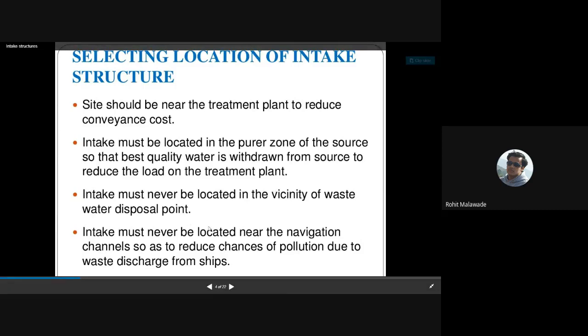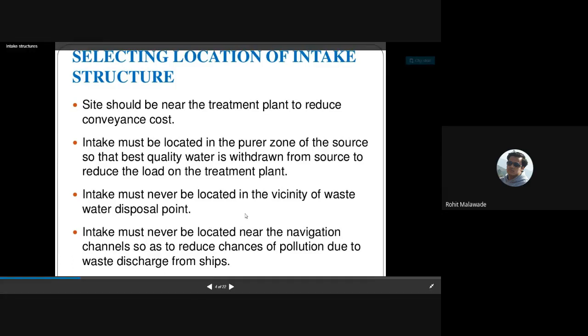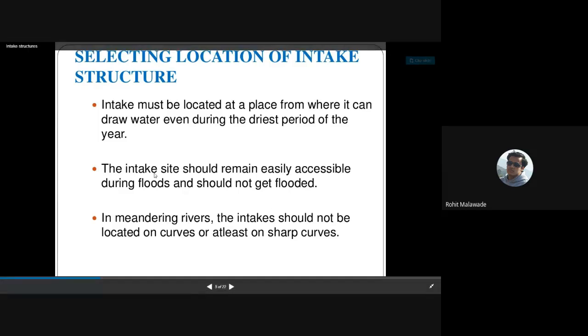The intake should not interfere with river traffic — boats and ships may be moving, so the intake structure should not affect navigation channels. The intake must be located at a place from where it can draw water even during the driest period of the year, including during the summer season.